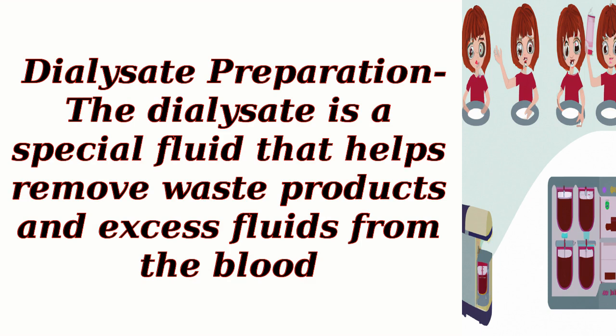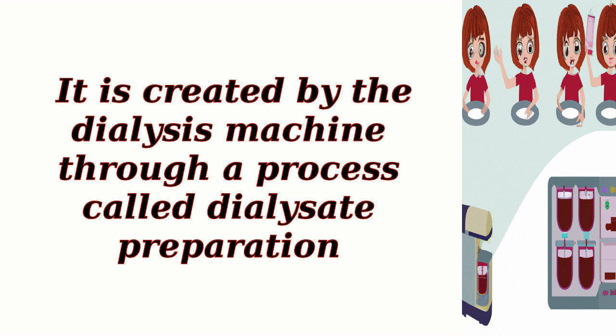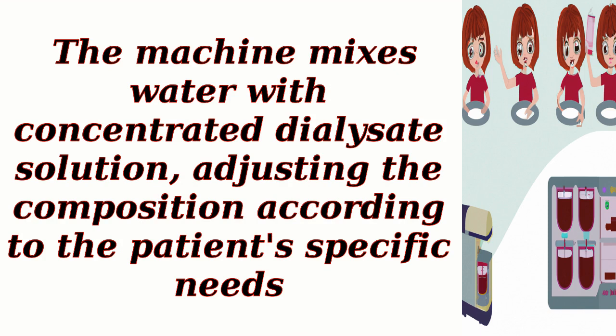Dialysate preparation: the dialysate is a special fluid that helps remove waste products and excess fluids from the blood. It is created by the dialysis machine through a process called dialysate preparation. The machine mixes water with concentrated dialysate solution, adjusting the composition according to the patient's specific needs.